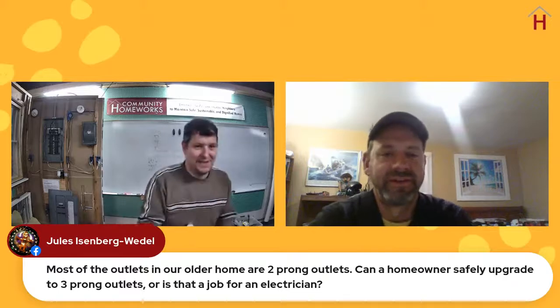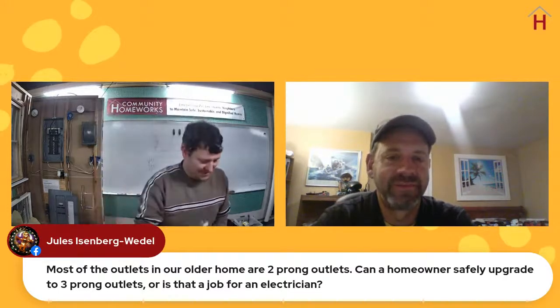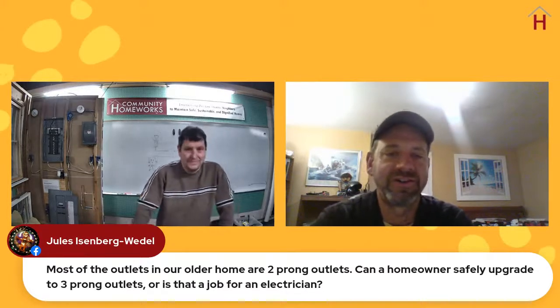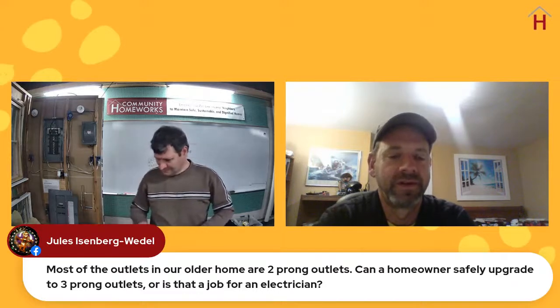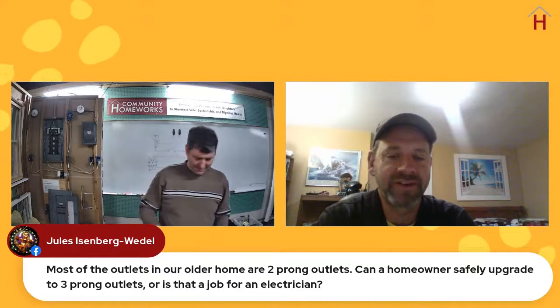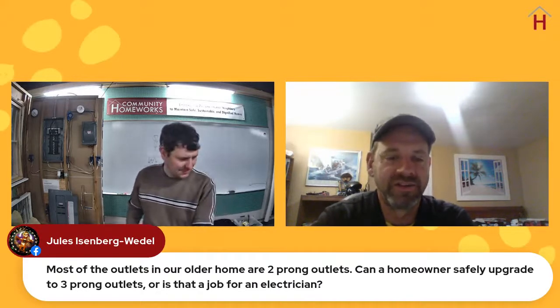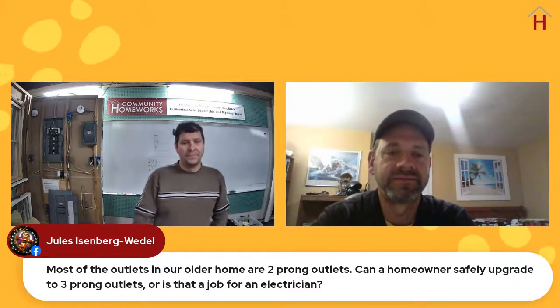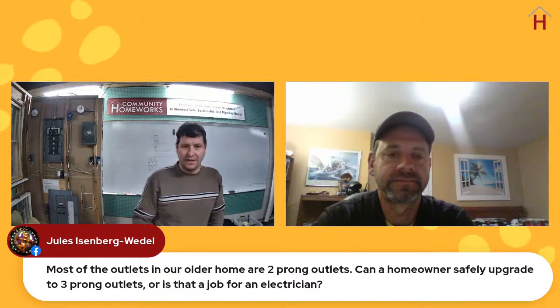Generally, it's not a hard thing to add if your boxes are grounded. I've run into only one home so far in your area where there were no grounded boxes, so grounding the box didn't give you a ground. Generally, if there's the metallic cable, which is called BX, normally that BX cable acts as a ground, or normally the newer Romex wire has a ground in it that will be grounded to the box, and then you can take a wire from the box to your green prong on your outlet, and then you can upgrade the outlets very easily. So once again, it's a limit on the wiring, not on the outlet, not on the breaker. It's a limit because of the wiring you have.